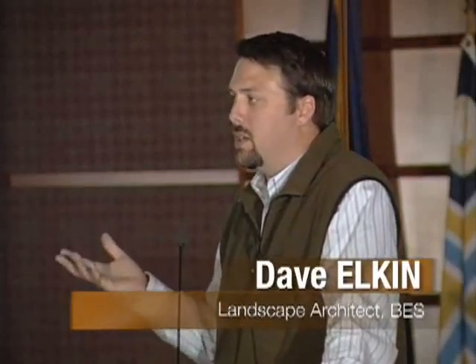If you're going to do an eco roof with an irrigation system and your client really is worried and is requiring one, well, have the provision that you're going to be replacing this thing in, I don't know how many years, but let's say 10 years or less. So consider that. One of the things that we've realized on this roof is that this was done with HDPE pipe and hose clamps. And we'll show you some more slides, but the UV, just expansion and contraction of that pipe causes that pipe to actually walk right out of the ground, and then it's exposed to UV. And then we've also had some failures of that hose clamp. It was supposed to be kind of more of a temporary system, but yet there's just some functional issues of having that sun on it all the time, that it's bursting and those kinds of things.